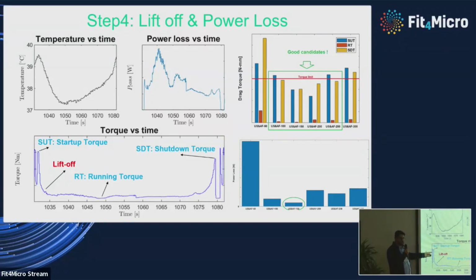What you see here is the frictional torque, which means the resistance to the movement. At the beginning, when we just want to start the rotation, you see a big peak, a big rise in the torque. It means that it's resisting to move. And then as soon as the air film establishes, so here, for example, you're already at 30,000, 25,000, or whatever speed you're lifting off, your torque is minimum. And then you maintain this minimum torque all the time that you're rotating. So this establishes that you are lifted off.